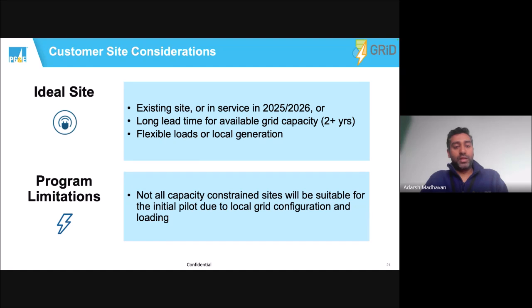The last thing I want to point out is not all capacity-constrained sites will be suitable for the initial pilot, because a great example would be line sections. We've had sites constrained by a 4-rod copper line, where the maximum capacity of that tiny line is 120 amps. There's no way FlexConnect can give additional available capacity because we literally have to reconductor that piece of conductor.